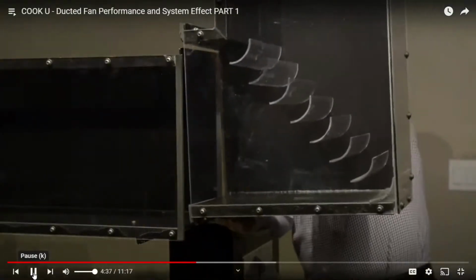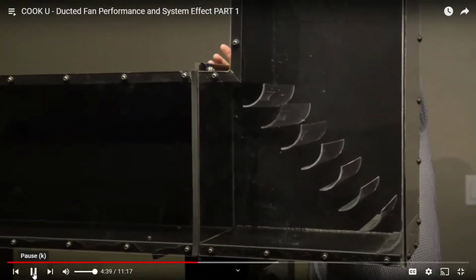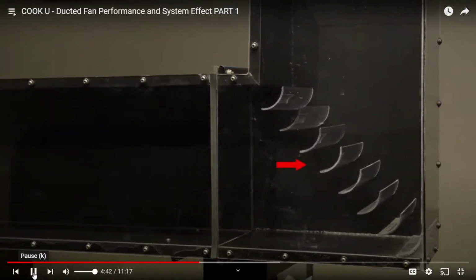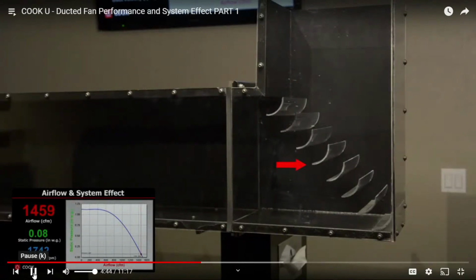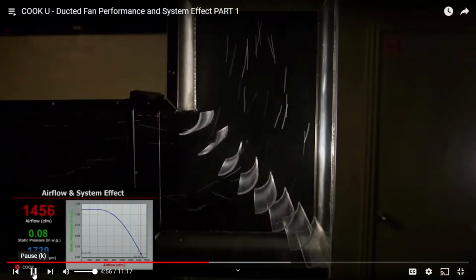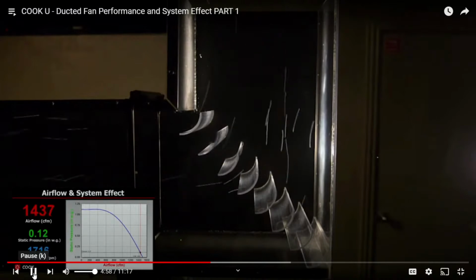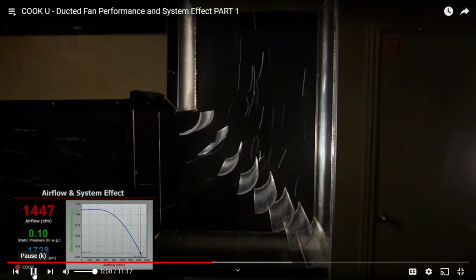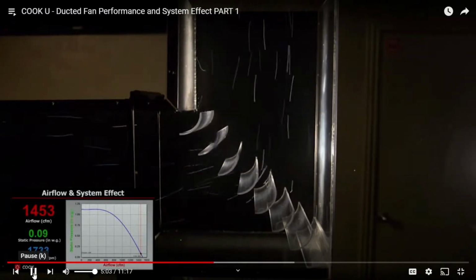You can see the problems that can arise when the system pressure is not fully accounted for. Moving on, let's replace this fitting with another. The second fitting is dimensionally identical to the first, but turning vanes have been added. This type of turning vane is known as a single thickness turning vane. By adding the turning vanes, you can see that we have reduced the pressure drop to 0.08, a reduction in pressure loss of 75%. Looking at our flow visualization, the airflow through the fitting is much more uniform with less turbulence, resulting in a lower pressure loss and greater airflow.